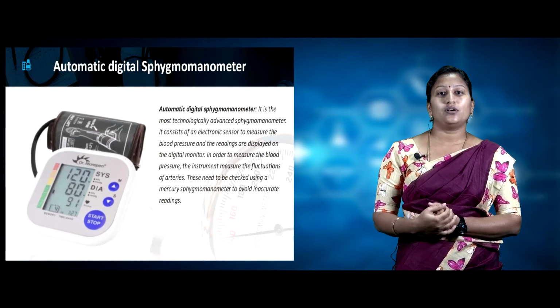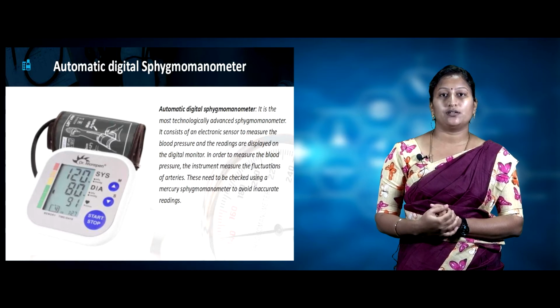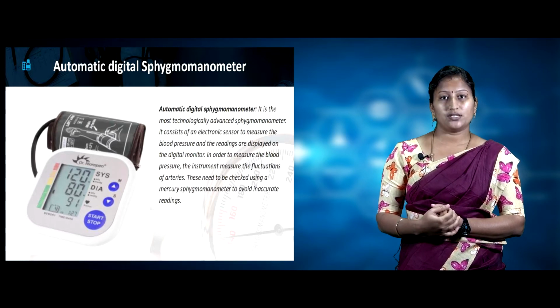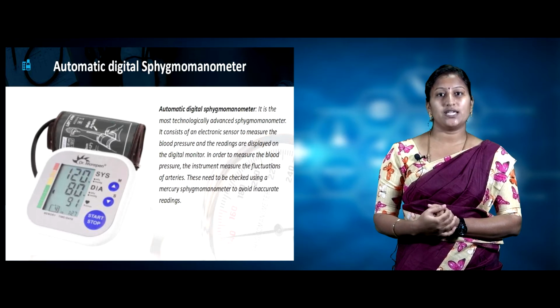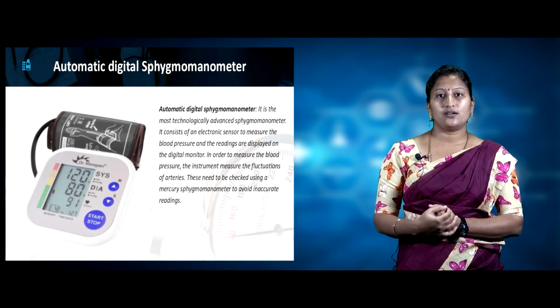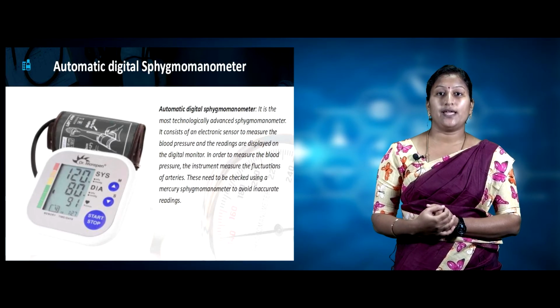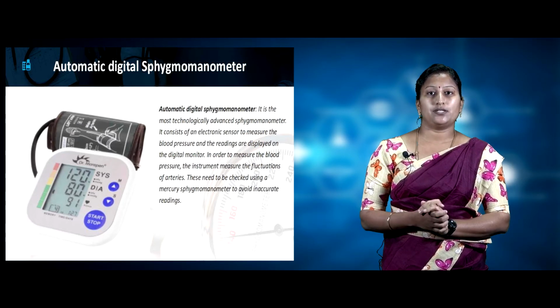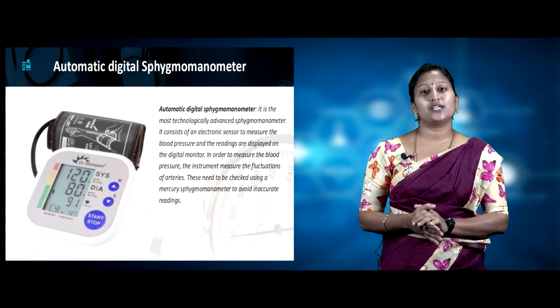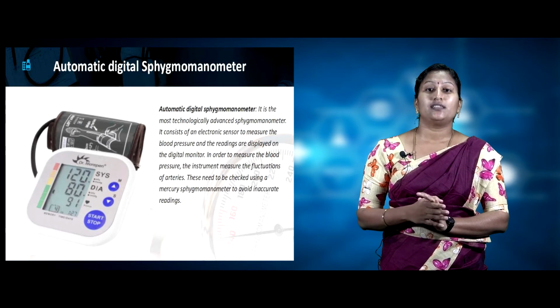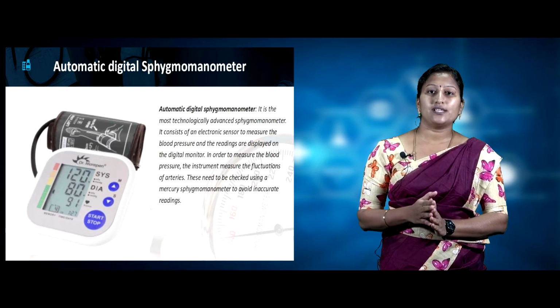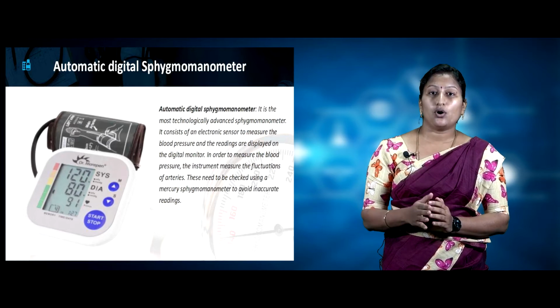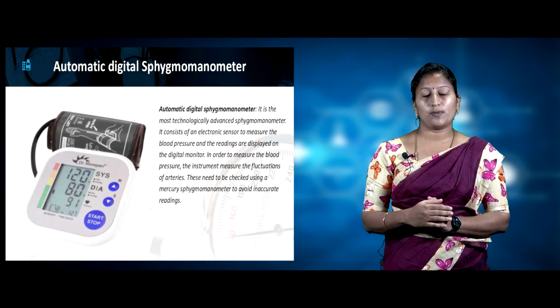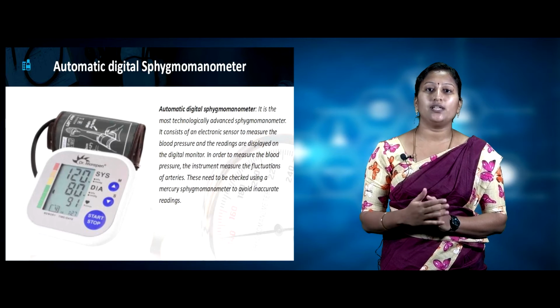Now let's see automatic digital sphygmomanometer. Automatic digital sphygmomanometers are the most technologically advanced sphygmomanometers. It consists of an electrical sensor to measure the blood pressure, and the readings are displayed on the digital monitor. To measure the blood pressure, the instrument measures the fluctuations of the arteries. These sphygmomanometers have to be cross-checked with the normal conventional mercury sphygmomanometers in order to avoid inaccurate readings.